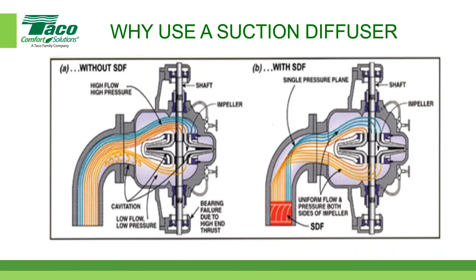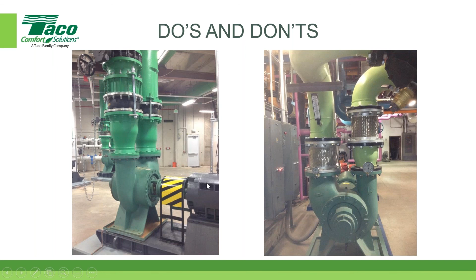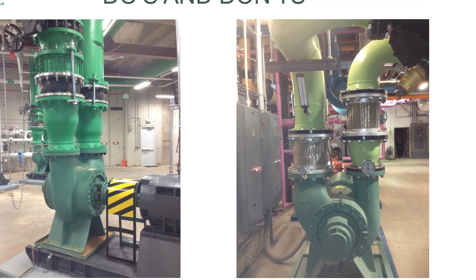So something to consider. Here's just one picture. On the left is a good do, and on the right is a don't, maybe. See how uniform this is, straight up. There are no forces on this. This is nice and clean. If you look close here, can I zoom in on this? You can see how this coupling flex is strained, right? This could cause some issues. You can see stresses being put on that pump, and something could be happening in that regard. That is just something you've got to look out for and try not to allow to happen as you go through it. So some things to consider there.